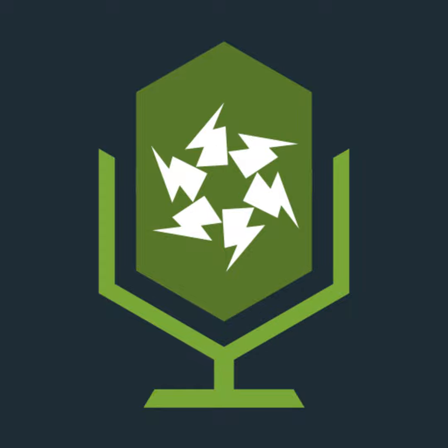Okay, so there is a potential for parallel arcs, but the series one is more interesting, and this is just where you have arcing in a series connection, a loose connection. It's dictated by the fault. There's no short circuit, there's no high current, and it's just a case of how long that fault should be there.